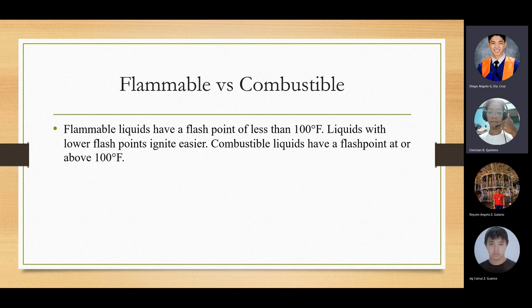Flammable versus combustible: flammable liquids have a flashpoint of less than 100 degrees Fahrenheit. Liquids with lower flashpoint ignite easier. Combustible liquids have a flashpoint at or above 100 degrees Fahrenheit. This shows the limit between flammable and combustible liquids, and that liquids with lower flashpoint ignite more easily.